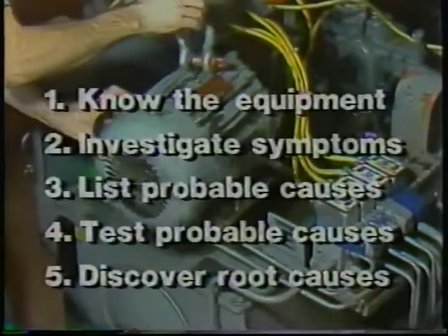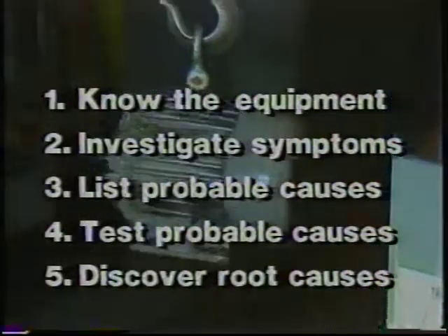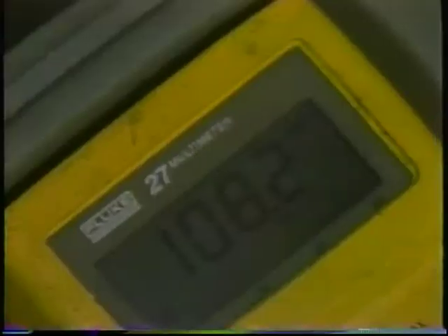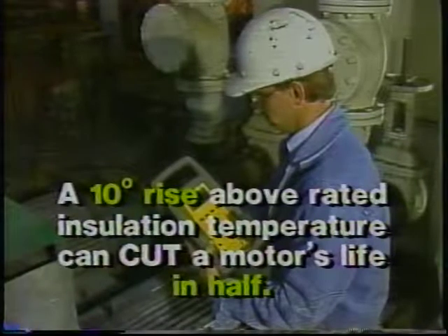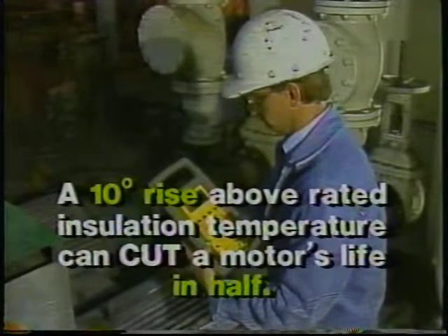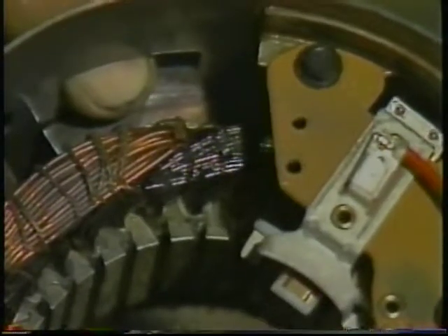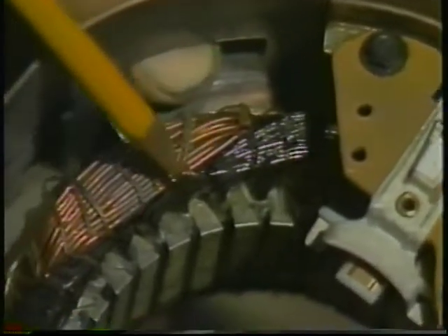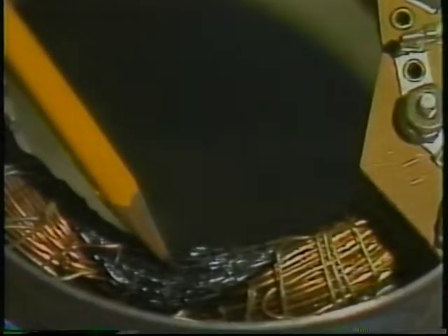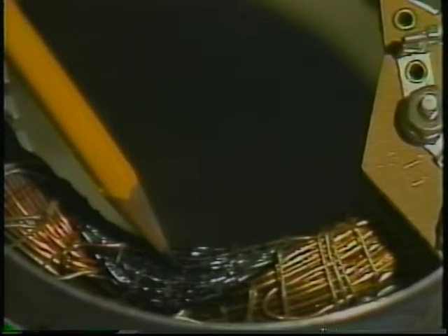Now, we have seen how to use the troubleshooting method to pinpoint the cause of a motor problem. But as we said, the troubleshooting process is not finished until you have determined what caused the cause. Some general principles about why motors fail may be helpful before we finish. Most motor problems are associated one way or another with heat. The general rule of thumb is that a motor's life is cut in half by a 10-degree rise in operating temperature above its insulation rating temperature. High temperature causes insulation breakdown and shorts between winding turns or between a winding and ground. Current in these shorts produces more heat, which accelerates insulation breakdown in a runaway process that eventually burns the motor out.